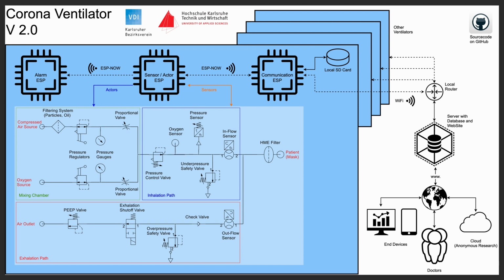This requires an additional proportional valve as well as a relative pressure sensor. The control loop is calculated on a sensor actuator ESP. It now, depending on the resulting pressure in the system, controls the inhalation airflow with the proportional valve.